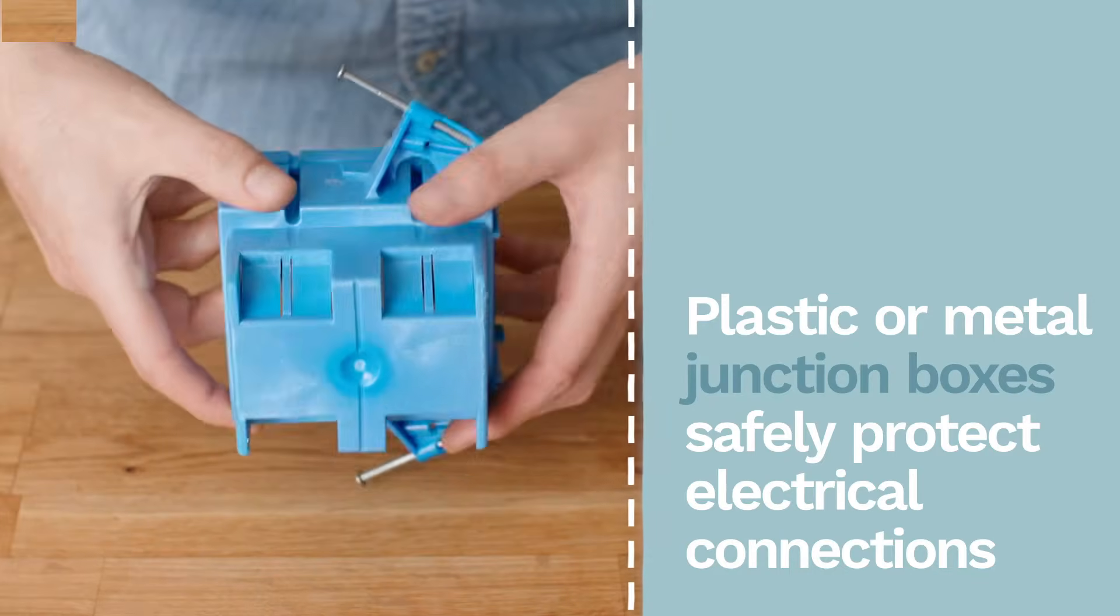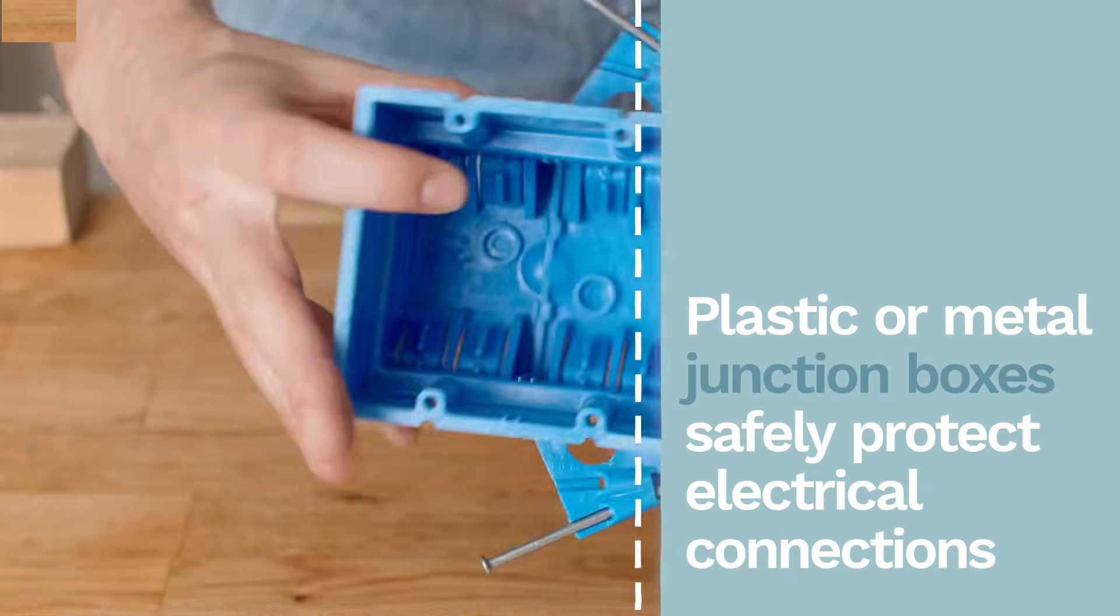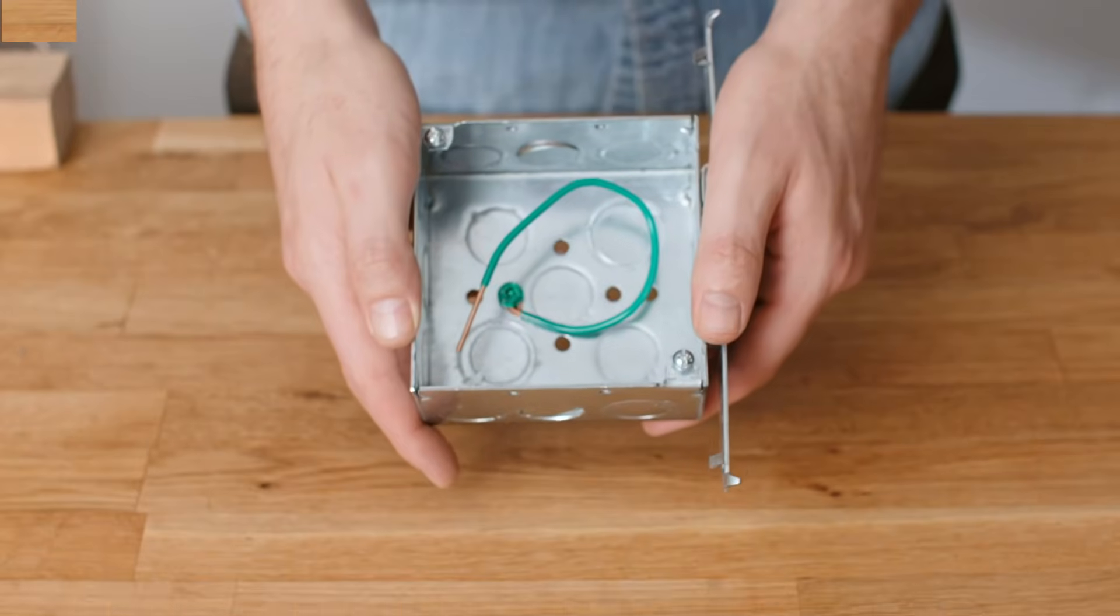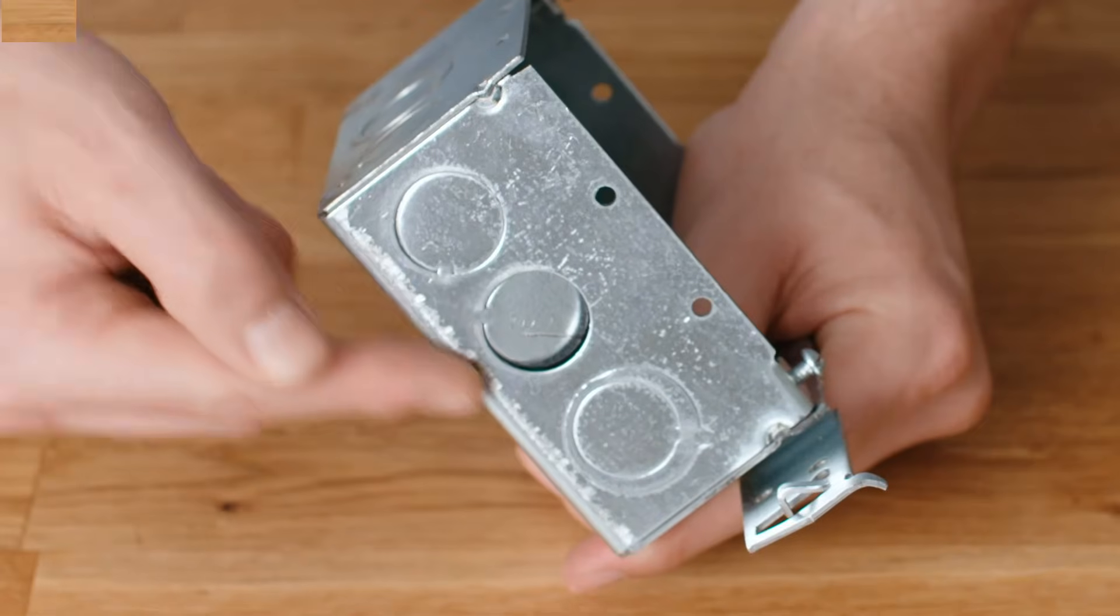A plastic box usually has internal tabs or clamps for securing the electrical cables. You can also add separate clamps if necessary. A metal box should have a ground wire and may or may not have internal clamps. If you need to add a clamp, remove a knockout plug and install a clamp into the hole.